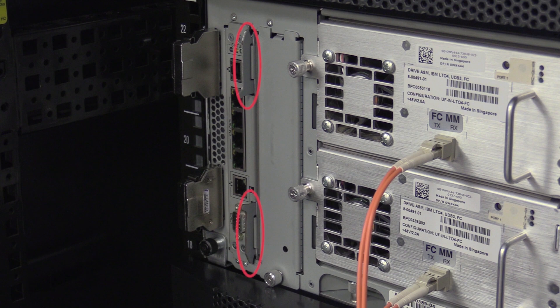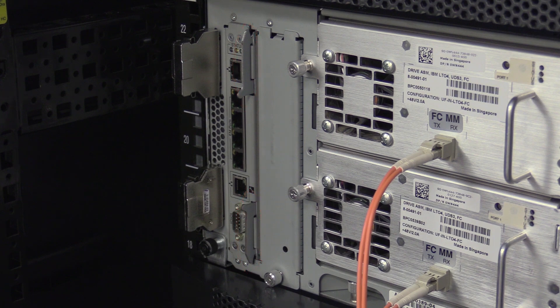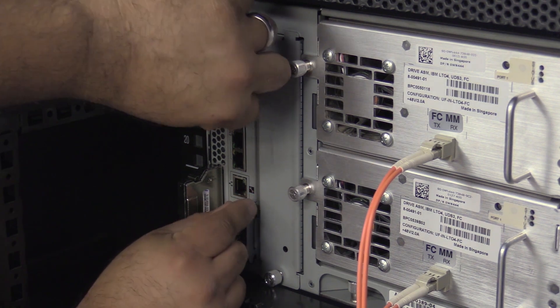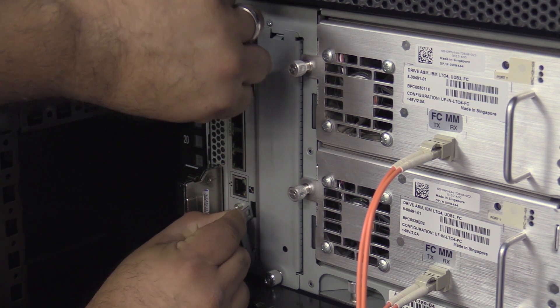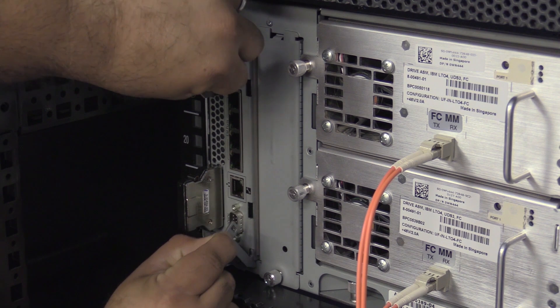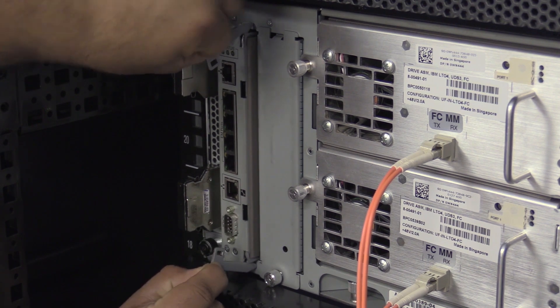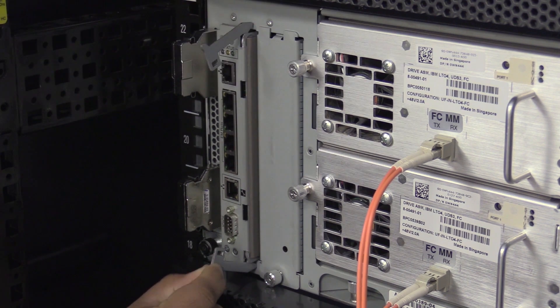You will not need any tools for this procedure. The control card is held in machine by two wing latches. You will need to push these latches in slightly to unhook them from the clips that hold them. You can then open the latches. As you open them, it will start pushing the card out of the machine.